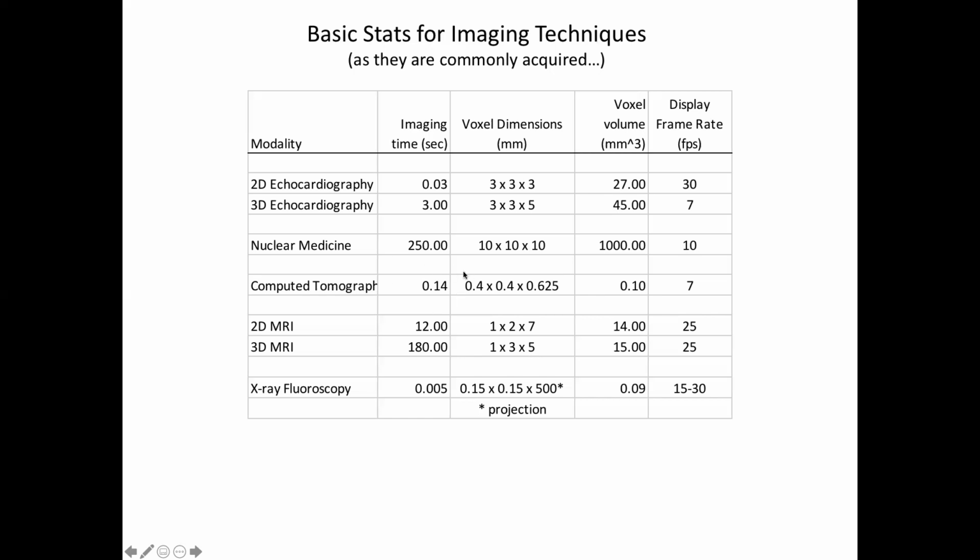And then there's CT, where the patient is lying in the scanner. We'll see pictures of all these. The gantry is rotating around the patient quite quickly, about 4 times a second. So when you turn the x-rays on, you get beams through the patient through that 360 degrees over 280 milliseconds, something like that. You only need half of them to actually reconstruct an image.